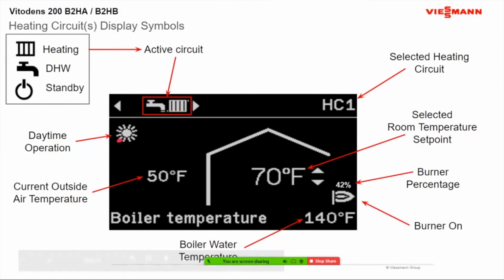With the startup wizard, once you're done, it will automatically put it in the standby mode. If you put heating circuit 1 in standby mode, you might not have heat. Heating circuits are different than zone circuits. With zone circuits, the newer way, I call it newer, but it's not really new, if you see it's in standby mode, you're fine, because with the zone circuits, we're waiting for an end switch to make contact. And then if it goes into domestic, the sensor takes over and tells it to go into domestic. So that's why it puts it in standby on the zone circuits.